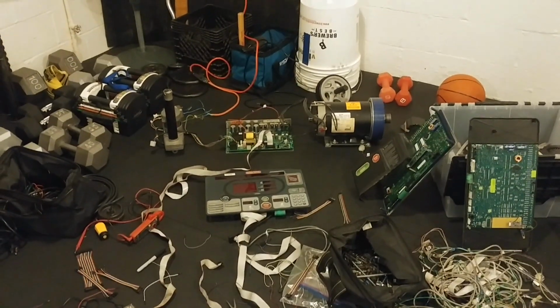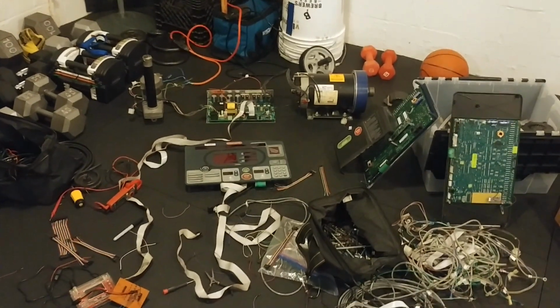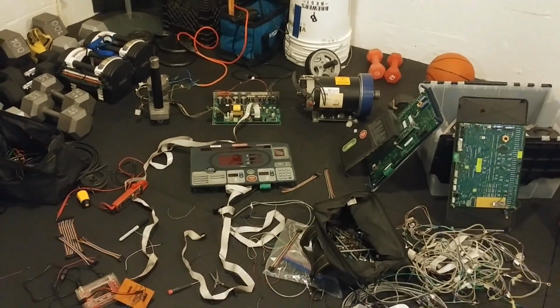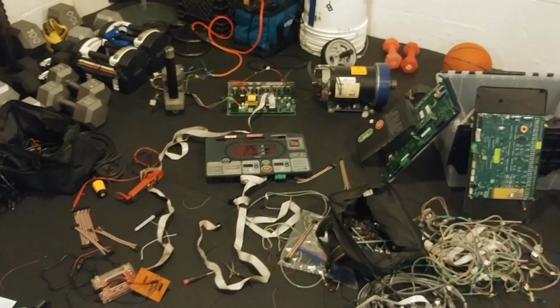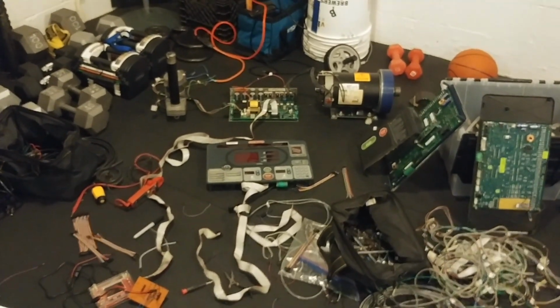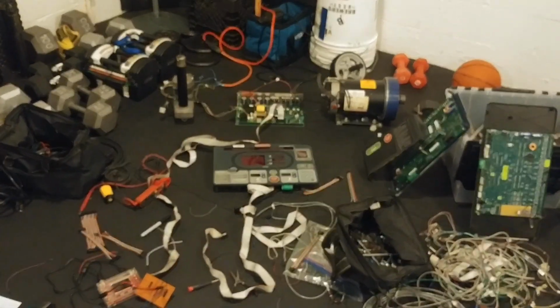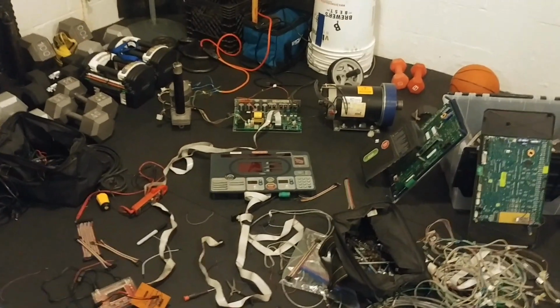So we were kind of lucky that the motor control could pretty much be isolated from everything else on the board. And the communication between the display and the VFD was not that advanced. It was more than a basic potentiometer motor controller, but it wasn't crazy with DRM and encrypted TCP or any of that sort of nonsense. So with some troubleshooting and critical thinking, we were able to figure out at least the important parts.